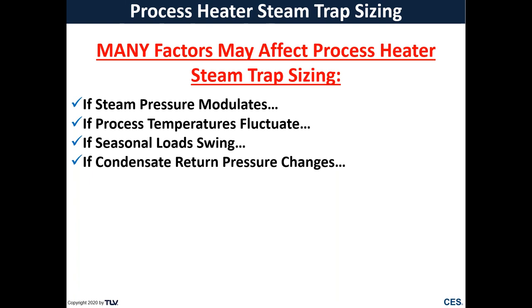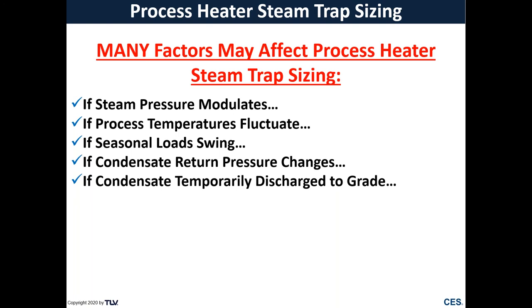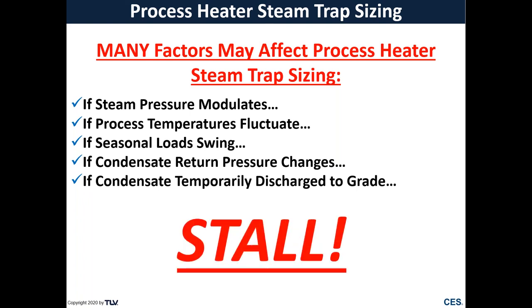Also need to consider if my condensate return line pressure changes, or if I temporarily discharge my condensate to grade. So all of these things are going to greatly affect how we size and select a steam trap. And most importantly, we cannot avoid considering the heat exchanger going to what we call a stall condition.